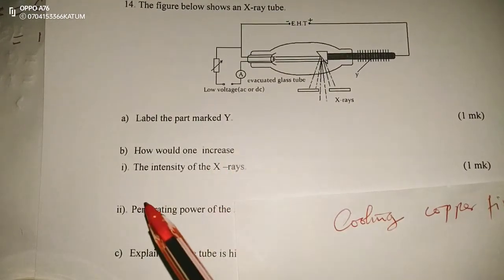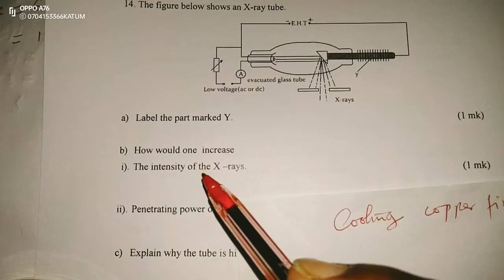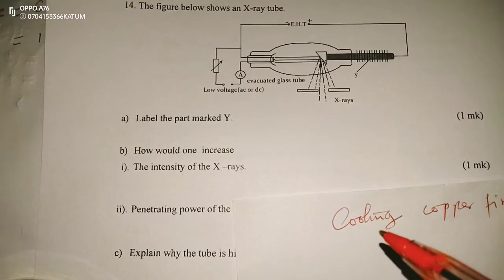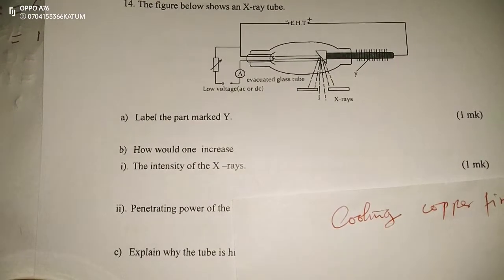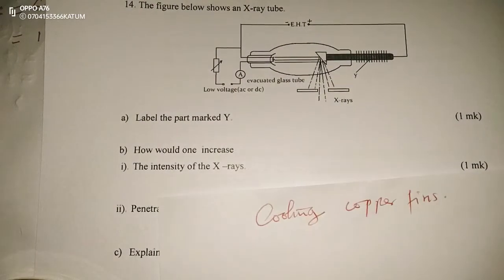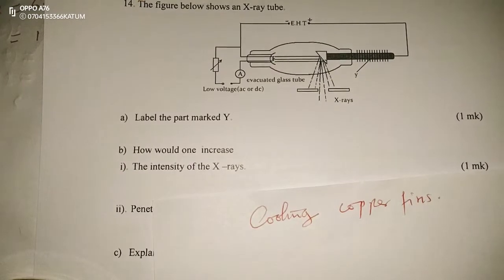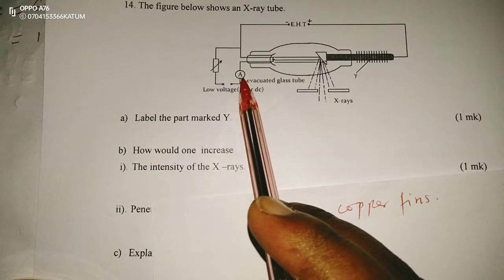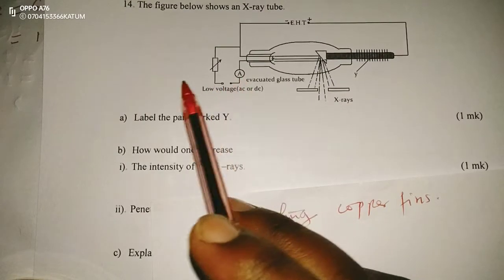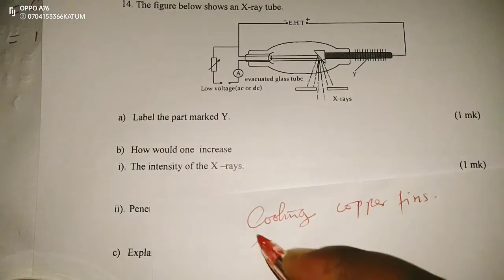How would one increase the intensity of the X-rays? The intensity of X-rays is the number of X-rays produced, and that is done by increasing the current. Remember we have a resistor and an ammeter here where current is being detected, so we can regulate the current by increasing it.